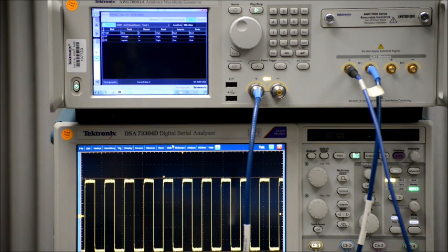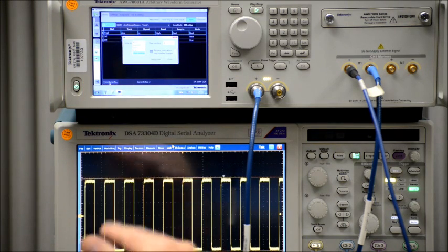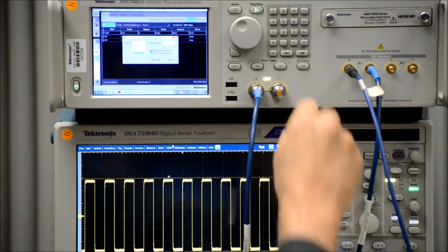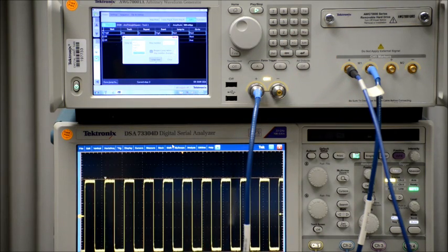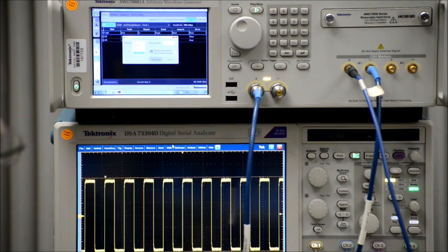And what we can do also is, say you want to go to a particular waveform in the list of waveforms that you have here, rather than going through them sequentially. You can pick a waveform number and then go to that particular number. So if I put in 3 here, I can select jump now, and it goes to the square wave, which is index 3. You can also use a general purpose knob if you want to scroll through these events or indexes. So let me close this.